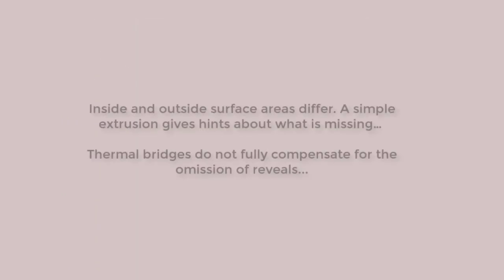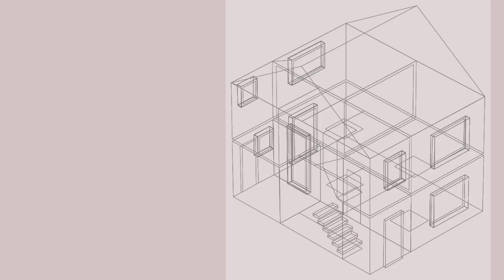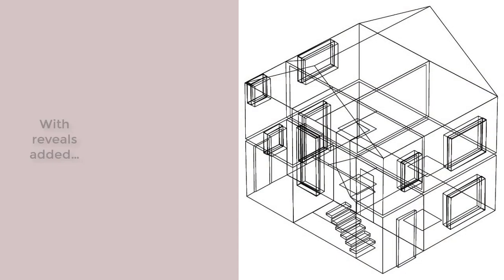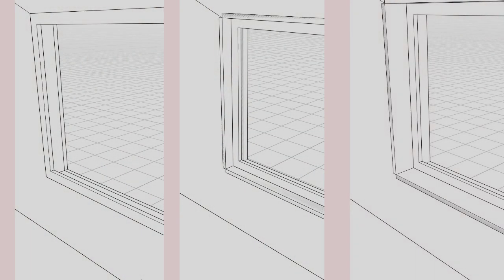One key point is that the outside surface area differs from the inside, and a simple extrusion of the polygon fails to capture this. The second point is that inclusions of thermal bridges do not fully compensate for the missing surface area of the reveals. To illustrate the impact of reveal decisions, let's have three variants: one with flush frames, one with a 100mm internal reveal, and one with a 200mm reveal.